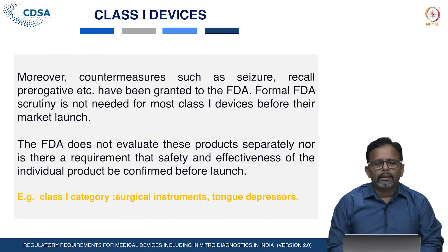The formal scrutiny of the application by the FDA for class 1 devices is not required prior to launch of the product into the US market. The FDA does not evaluate the product separately, nor is there a requirement that the safety and effectiveness of class 1 devices be established before launch of the product into the market. So, only the general controls are there for class 1 devices in USA.